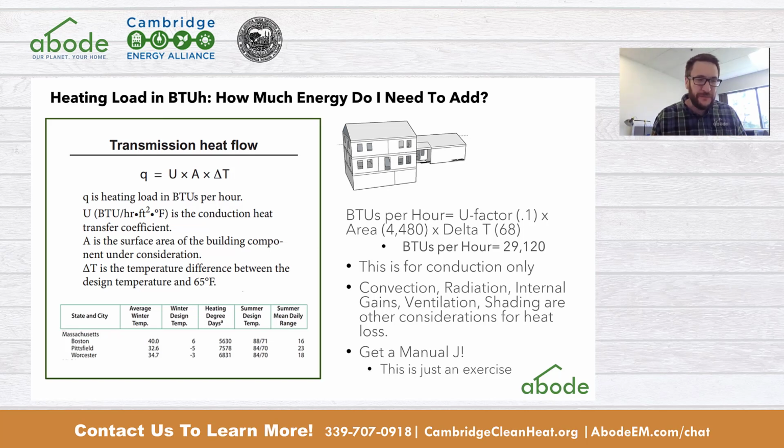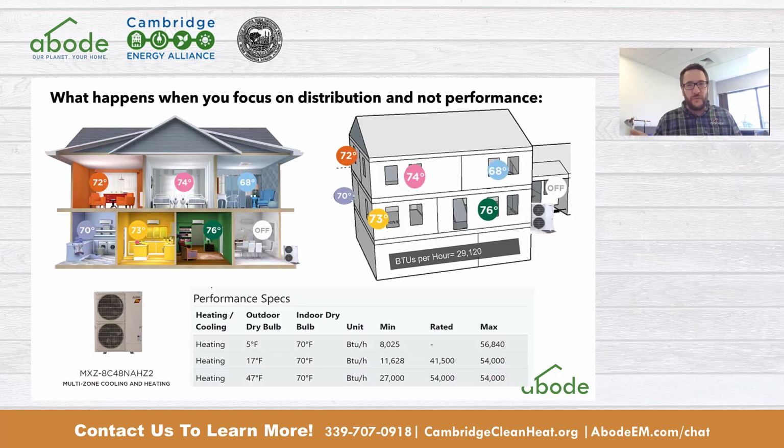But now there's really robust software called the Manual J. You take measurements of all your windows, all of your walls, the height, the insulation, the shading, the U factor and the glazings, and it pulls together, if the installer does it correctly, a room by room exact measurement of how much heat is going to be needed to keep it at temperature and how much cooling and humidity removal is going to be required in the summertime to keep that room comfortable. That's called the Manual J report, and it's so important. So we're going to be dealing with a Manual J of 30,000 BTUs.